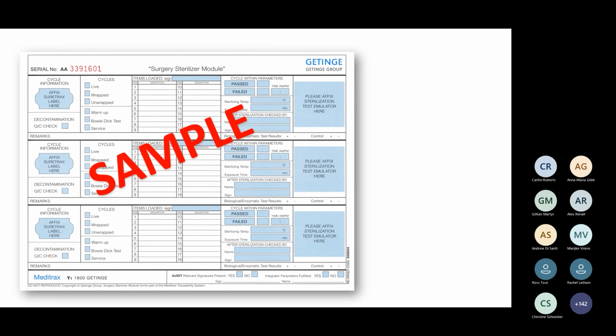The only time you need to put incision kit 1, incision kit 2, incision kit 3, or something like that, is if you have set packs that are actually sterilized and all the instruments always stay together. If you don't have an instrument pack where all the instruments are totally together all the time and never swapped out with any other instrument, then you can simply put incision pack by 5. Because if you're constantly changing the instruments around that are in that pack, you can't tell which instrument was in which pack. So it's totally irrelevant if you put pack 1, 2, 3, 4, or 5. It's just that you've got 5 packs in the machine. So that left-hand side is what you're going to be filling out to begin with when we load the sterilizer.